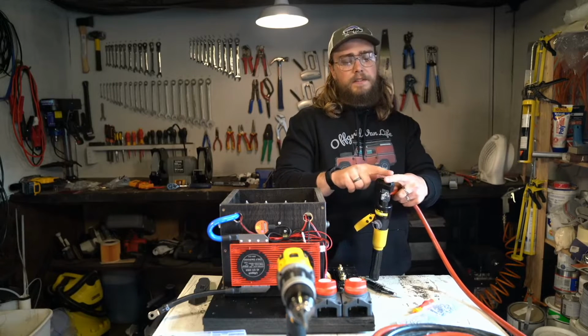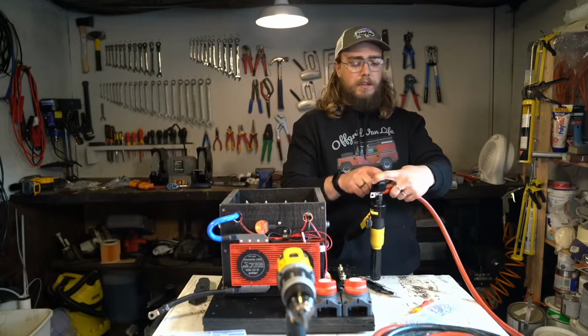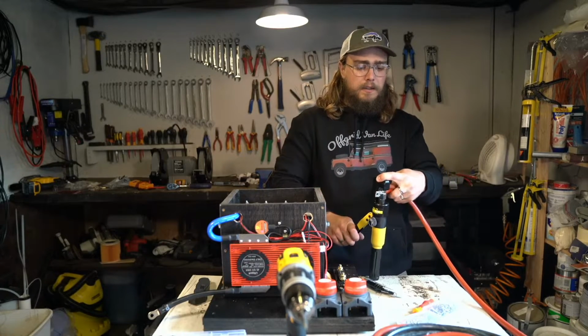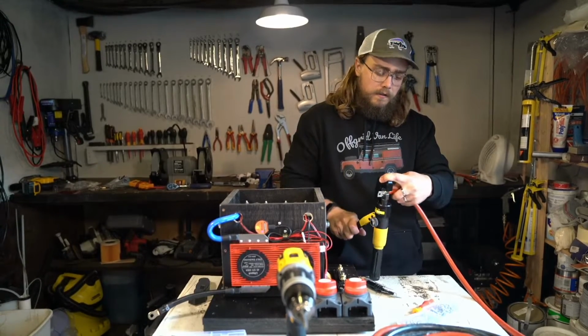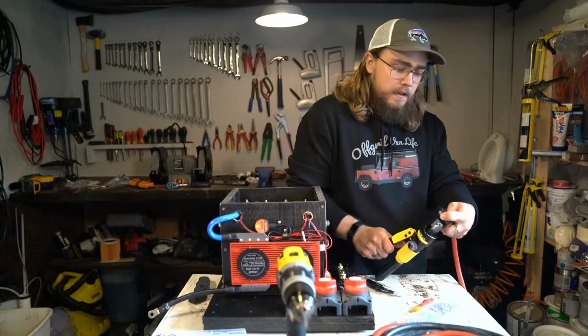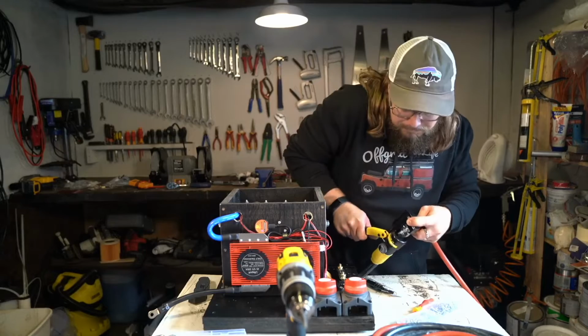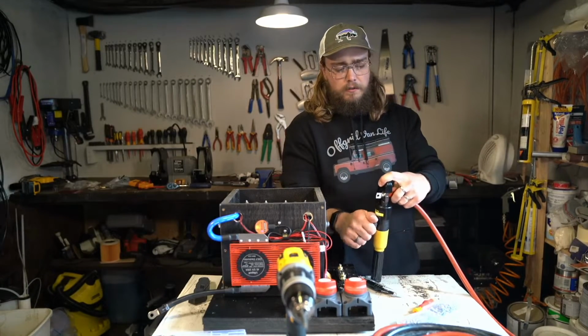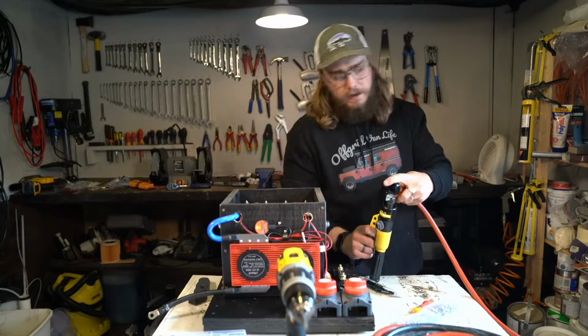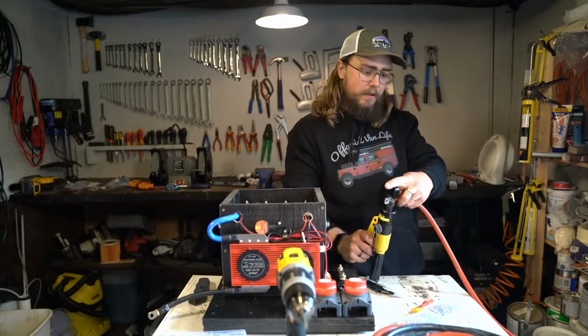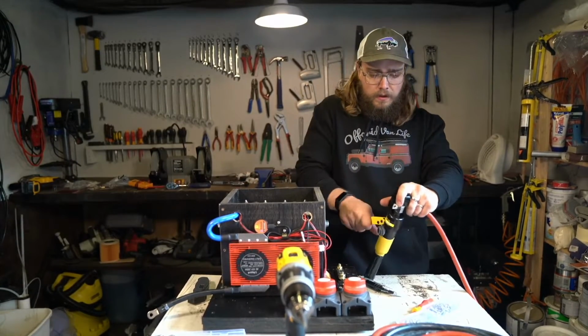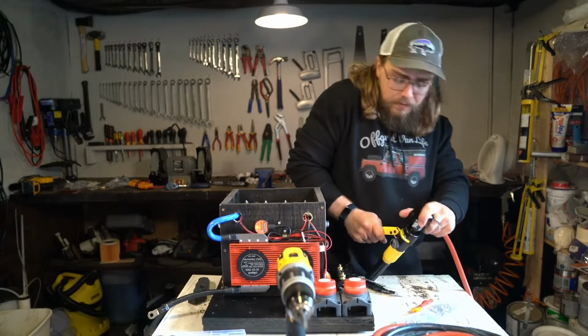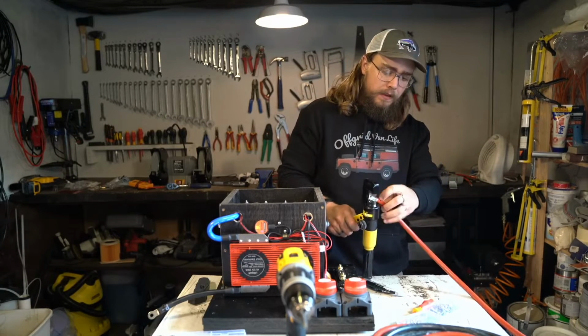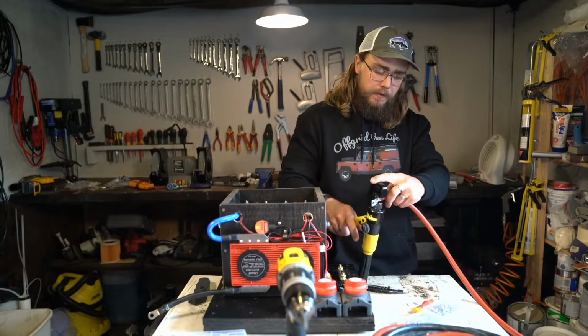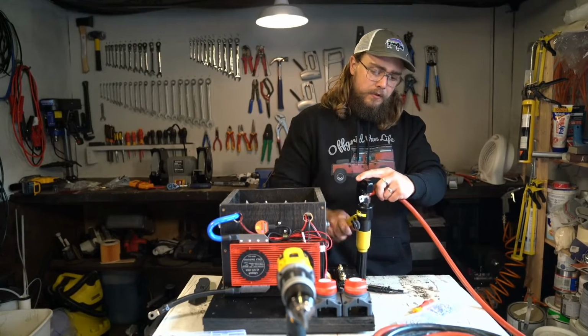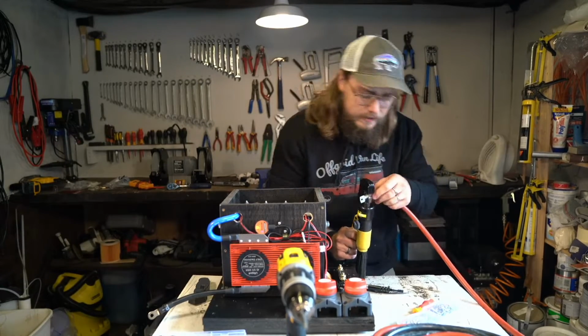So I like to put this index finger on the top of the jaws there, so I have some leverage, and then with my left hand I'm pushing the cable into the lug so it goes in as far as it'll go, then I rest the bottom of it on the workbench and keep compressing until I can't compress anymore, and then release it with that little dial on the side. Then I go and do it a couple more times along the shaft of the lug, to try and get as much of a cold weld there as possible.